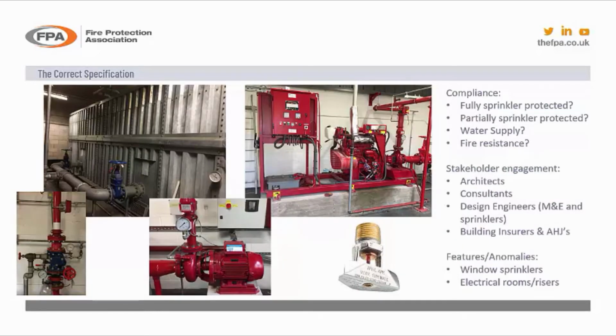So getting the correct classification of system for the risk is vital. Moving on, is the system required to meet compliance? Well, different standards have different requirements. For instance, the sprinkler system designed to meet building control for life preservation, which is the 12845, only requires 60-minute fire separation between sprinkled and unsprinkled compartments. So under the life safety standards, under the British standard, you can have permitted and necessary exceptions, such as enclosed staircases, washrooms and toilets that have got no storage in. So when you've got this scenario, fire resistance between compartments is only required to be 60 minutes.